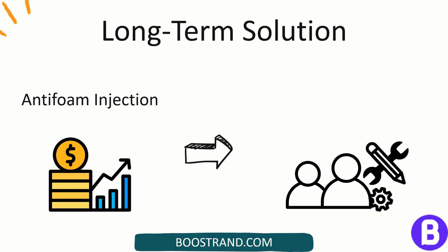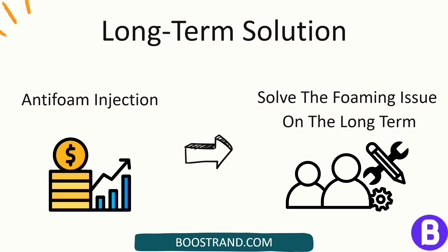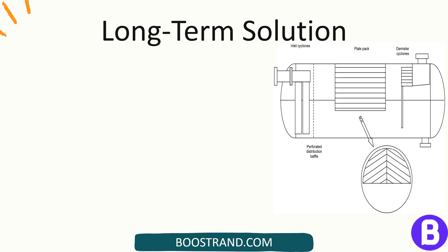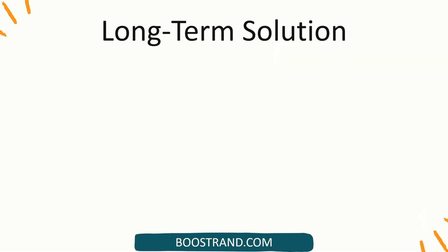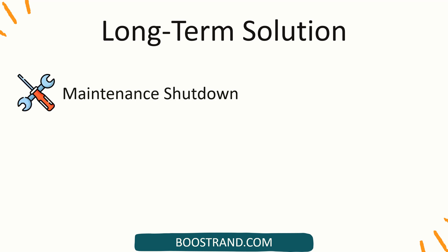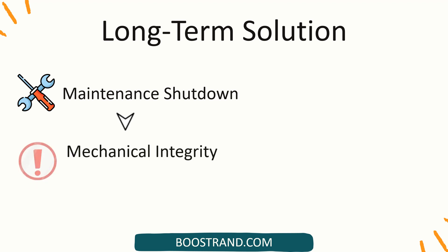That's why the engineering team sought to solve the foaming issue on the long term by contacting a vessel internals separator vendor. The internals supplier suggested a retrofit plan that included the installation of a new inlet device and foam-breaking plates. These internals were delivered and planned to be installed during the upcoming scheduled maintenance shutdown. There were great challenges related to welding these internals in the vessel as they can affect its mechanical integrity, but these were taken into consideration during the assessment phase made by the internals supplier.